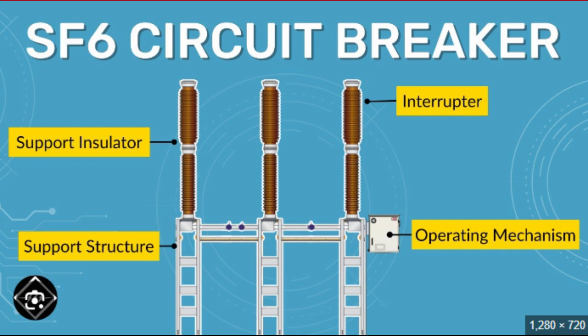In such circuit breakers, sulfur hexafluoride (SF6) gas is used as the arc quenching medium. SF6 is an electronegative gas and has a strong tendency to absorb free electrons. The contacts of the breaker are opened in a high-pressure flow of SF6 gas, and an arc is struck between them. The conducting free electrons in the arc are rapidly captured by the gas to form relatively immobile negative ions. This loss of conducting electrons in the arc quickly builds up enough insulation strength to extinguish the arc. SF6 circuit breakers have been found to be very effective for high power and high voltage service.